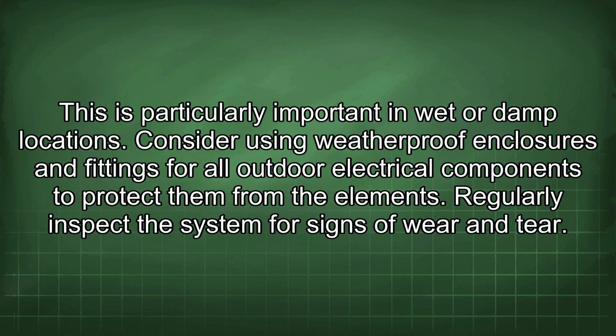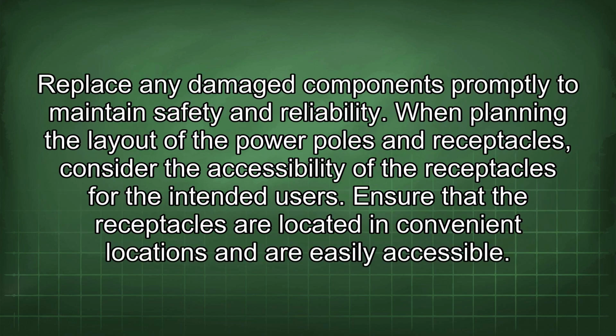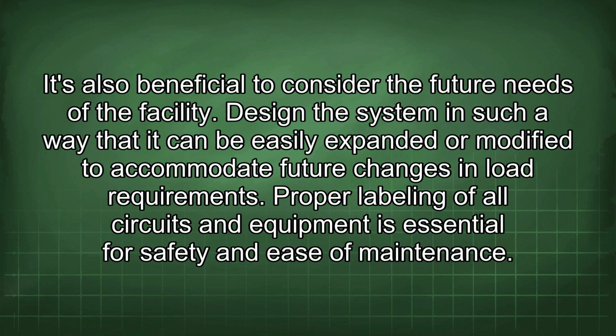Consider using weatherproof enclosures and fittings for all outdoor electrical components to protect them from the elements. Regularly inspect the system for signs of wear and tear. Replace any damaged components promptly to maintain safety and reliability. When planning the layout of the power poles and receptacles, consider the accessibility of the receptacles for the intended users. Ensure that the receptacles are located in convenient locations and are easily accessible. It's also beneficial to consider the future needs of the facility. Design the system in such a way that it can be easily expanded or modified to accommodate future changes in load requirements.